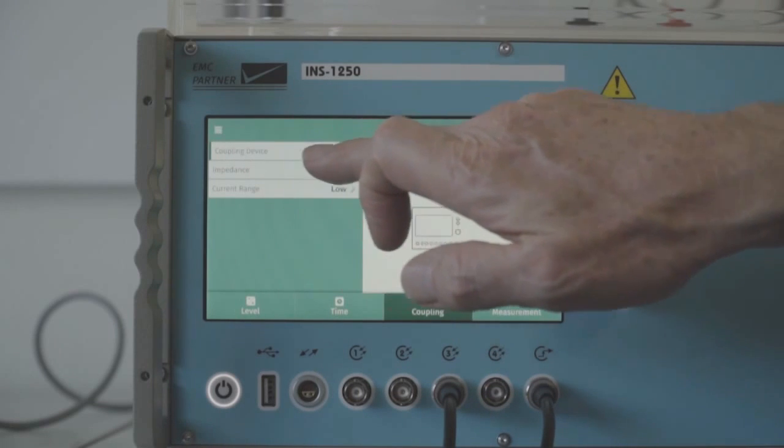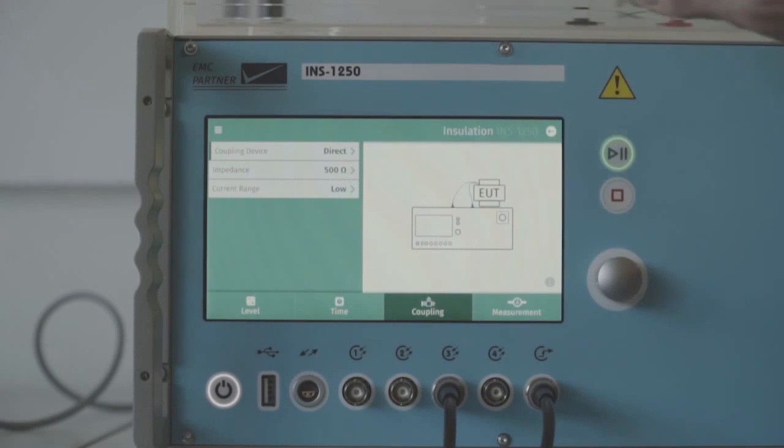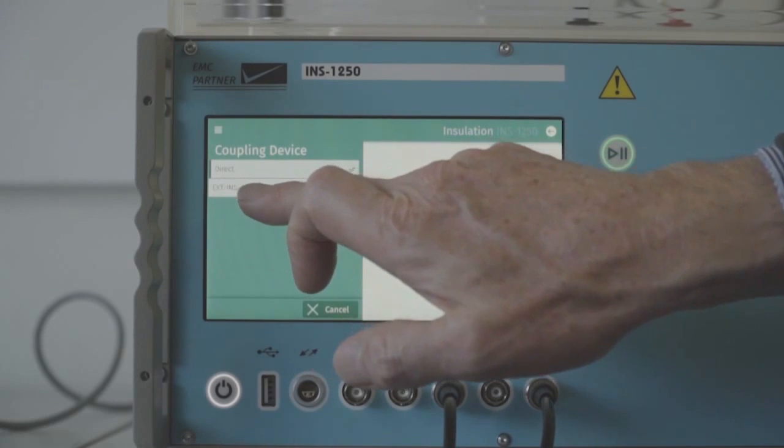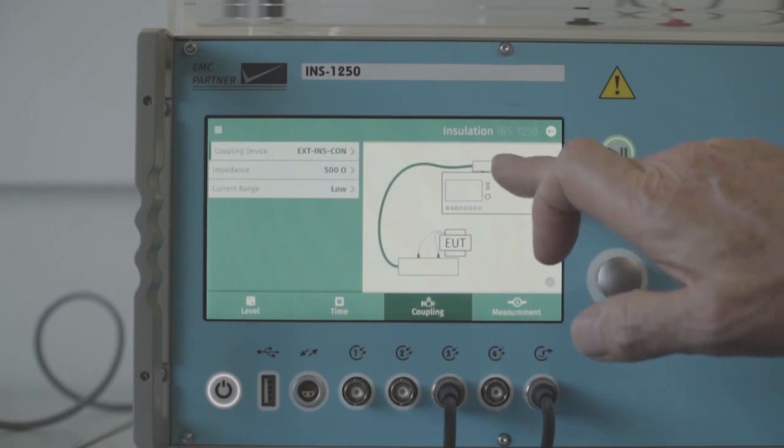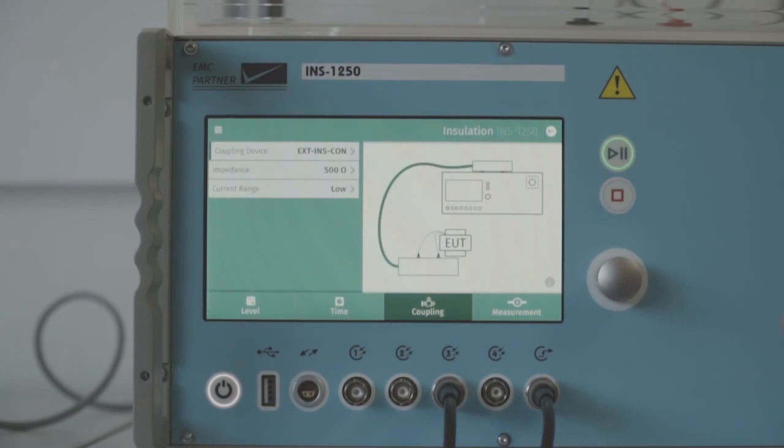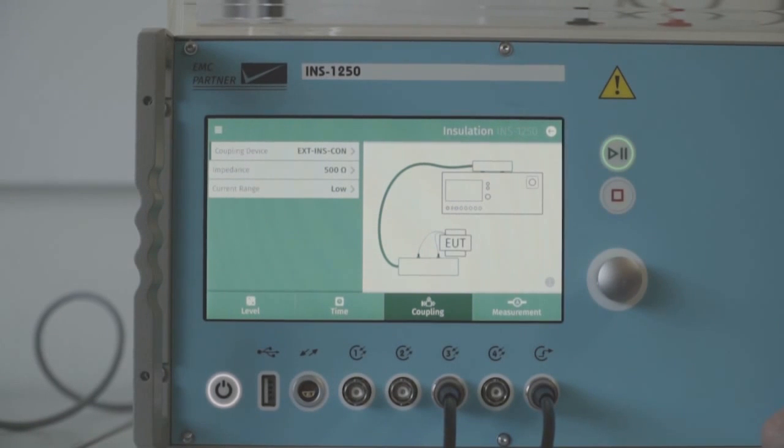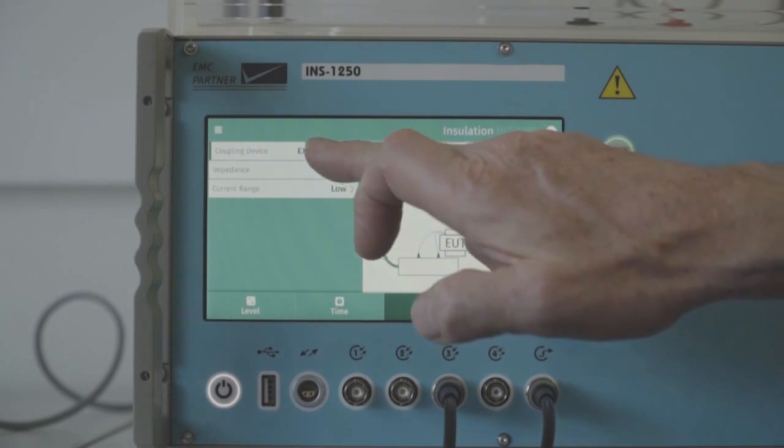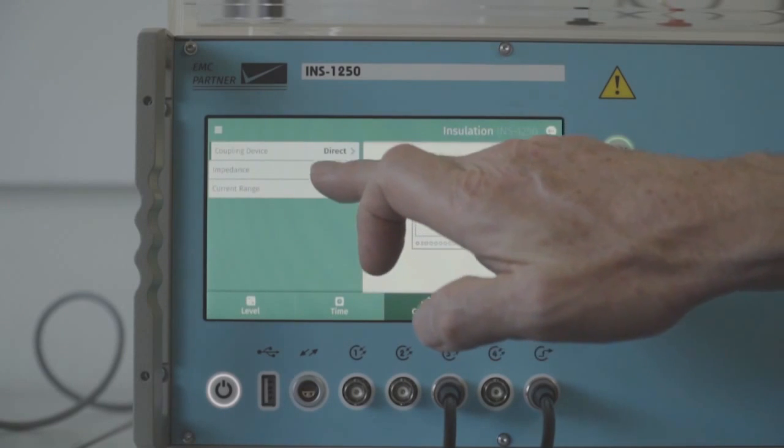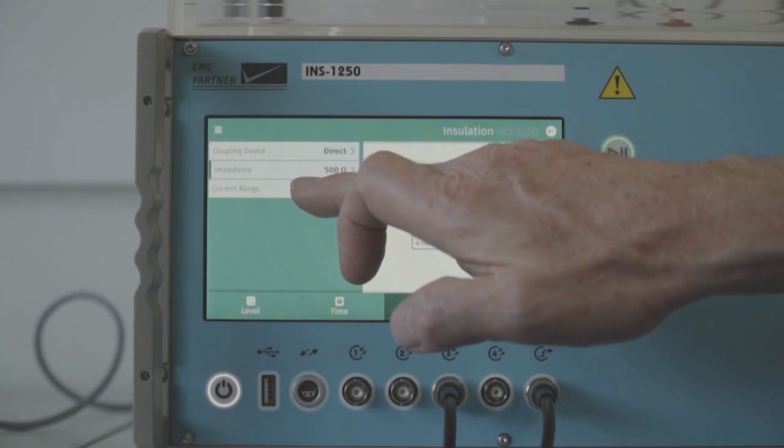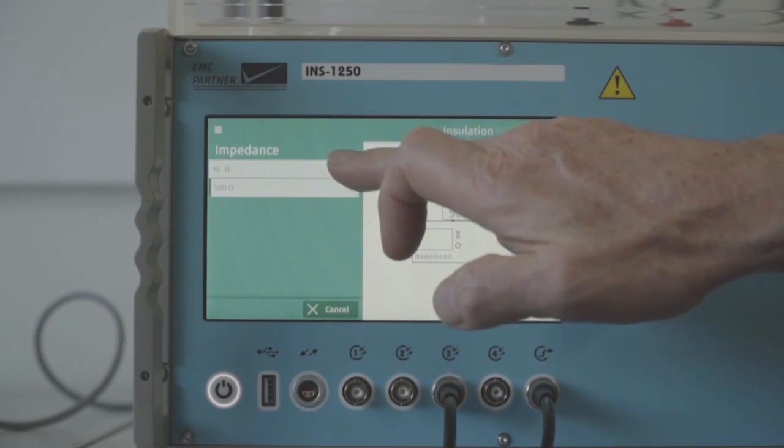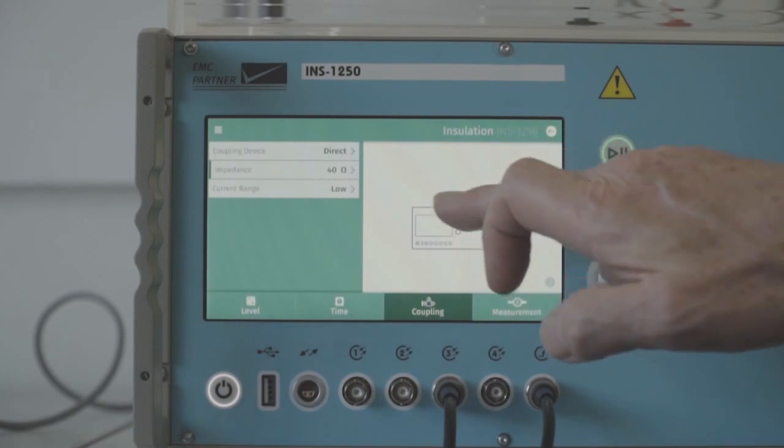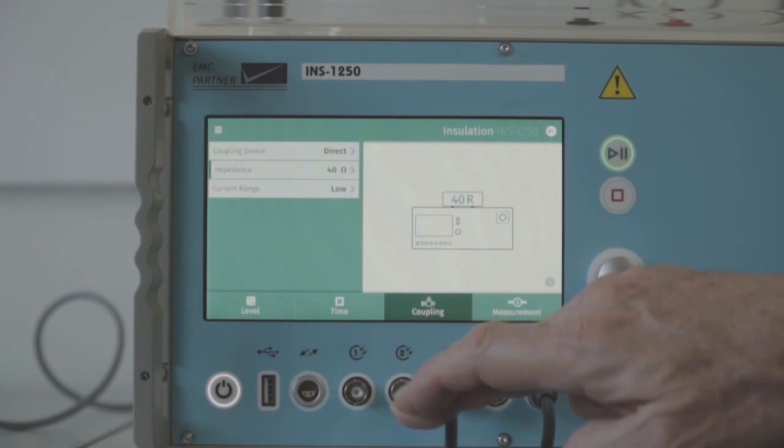Coupling. Direct coupling means connection directly on the top of the generator. If we select the EXT INS CON, this is a 2m cable which connects from the top of the generator to the test object, and at the end of this cable we guarantee that the impulse is within tolerance. We can also change the generator impedance between 40 and 500 ohm. 40 is the standard that we provide with the generator.